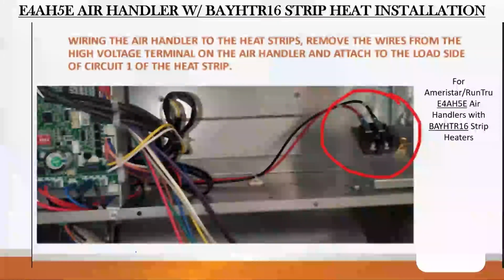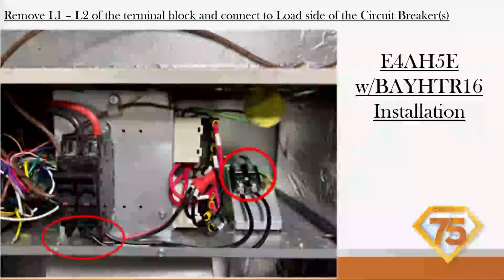So here's a picture of that L1, L2 terminal. This is without heat strip. When we do have heat strips in here, say 20 kW, both these plates come off. We're going to take L1, L2 right here, and we're going to strip off those spades. We're going to strip that back, and we're going to land it on the load side of the heat strip, right? So we're going to land that on the load side of the heat strip.